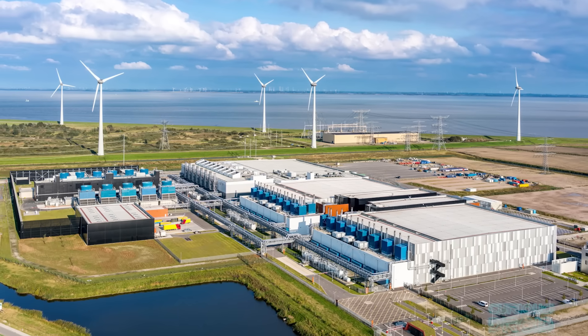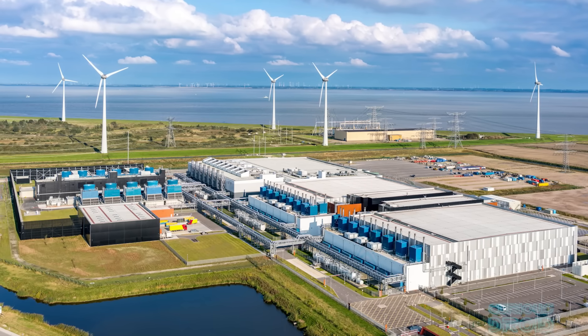This is why so many data centers are now being built either with associated wind and solar farms, or near geothermal or hydroelectric plants. Electrical power is the primary cost, which is one of the reasons why the UK has so few large data centers — electricity here is some of the most expensive in the world. A recent DOE report found that in the US in 2023, 4.4%, or 176 TWh, of all electricity generation went into powering data centers, and this is estimated to rise to between 6.7 and 12%, or 325 to 580 TWh, by 2028 — and this doesn't include all the tens of millions of end-user computers and smartphones those data centers are communicating with.